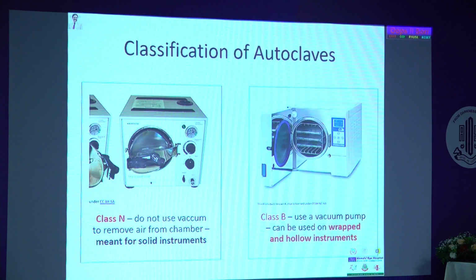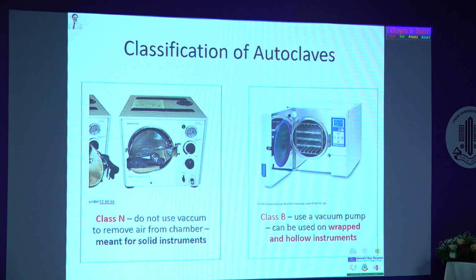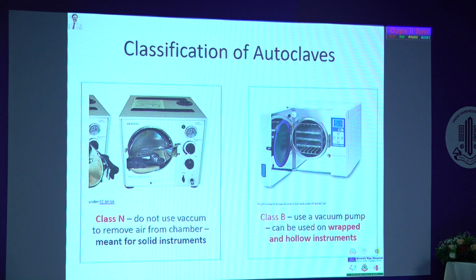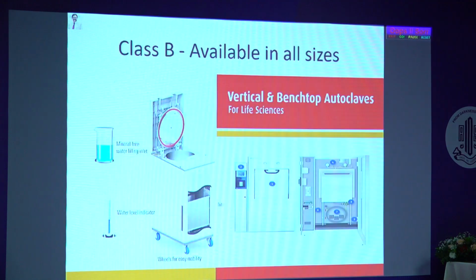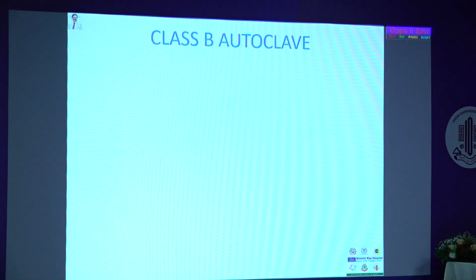Class N doesn't use a vacuum to remove air from the chamber. So this is basically meant for solid instruments. That is the reason why most dental units will be using this class N or class S. Class B is what we prescribe. It has a vacuum pump and can be used for wrapped and hollow instruments. In ophthalmology, if you are using these kinds of instruments, it's better to switch over to a B class autoclave. It is available in all sizes. There are bench top, tabletop, as well as large units.